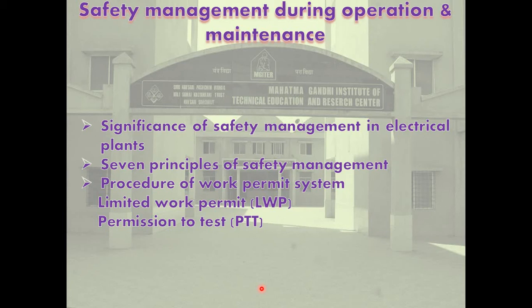During the construction period, the civil work, erection, transportation of equipment, etc. may progress simultaneously and many untrained personnel may be working at site, resulting in high risk of accidents. The risks of equipment failure, shocks, explosions, etc. are higher during first commissioning and energizing, as the equipment may have undetected internal faults. During operation, electrical energy can flow from the supply system into the fault and cause explosion. Overheating or short circuit can cause fires. Mechanical failures can cause accidents.